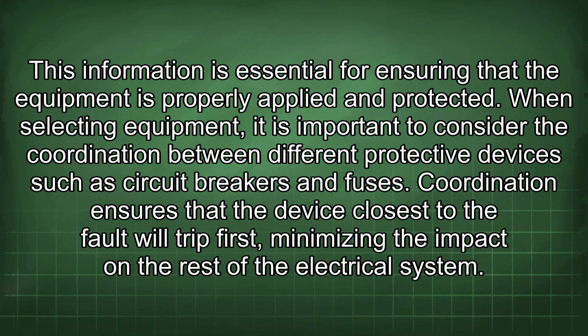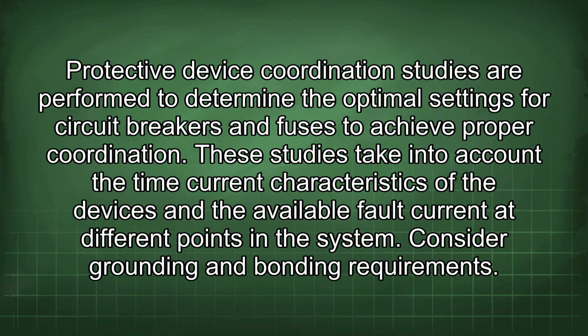When selecting equipment, it is important to consider the coordination between different protective devices such as circuit breakers and fuses. Coordination ensures that the device closest to the fault will trip first, minimizing the impact on the rest of the electrical system. Protective device coordination studies are performed to determine the optimal settings for circuit breakers and fuses to achieve proper coordination. These studies take into account the time current characteristics of the devices and the available fault current at different points in the system.